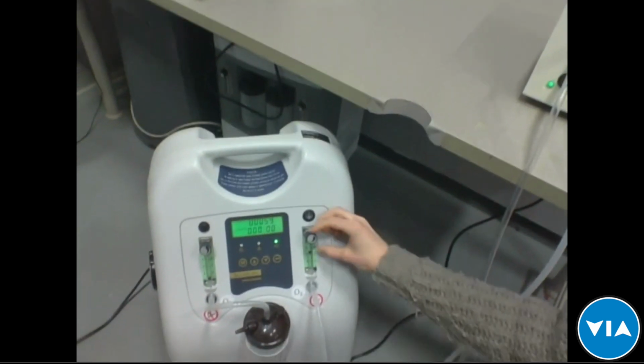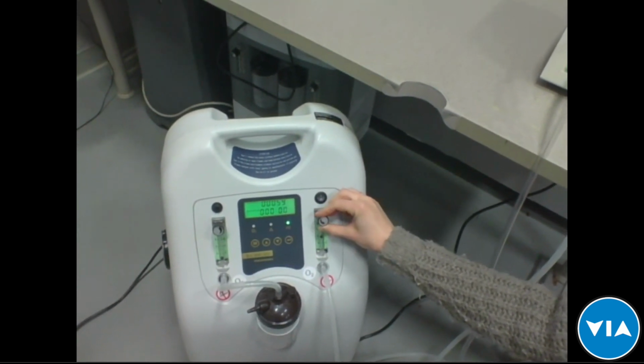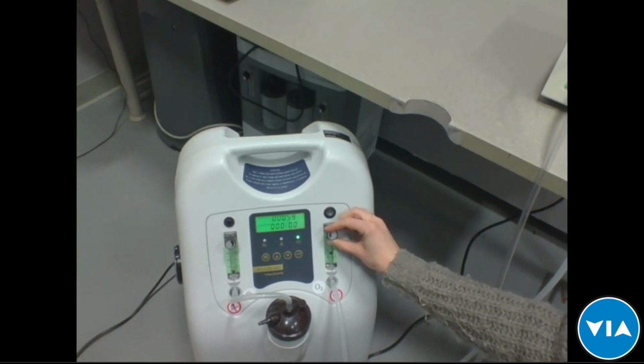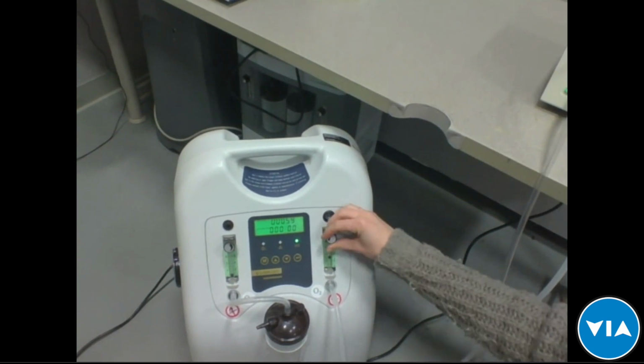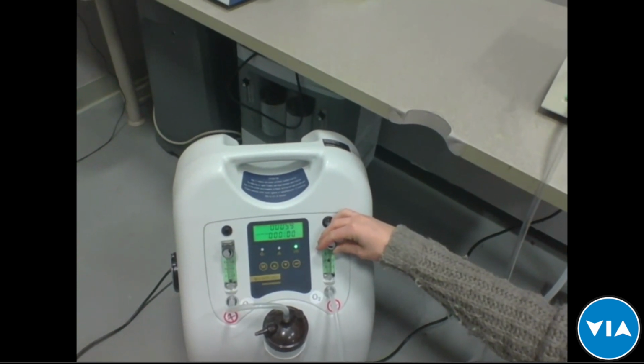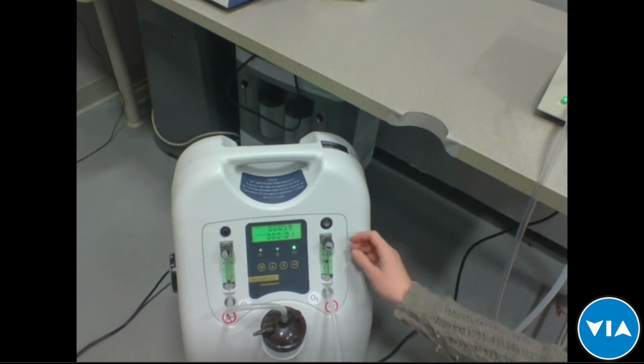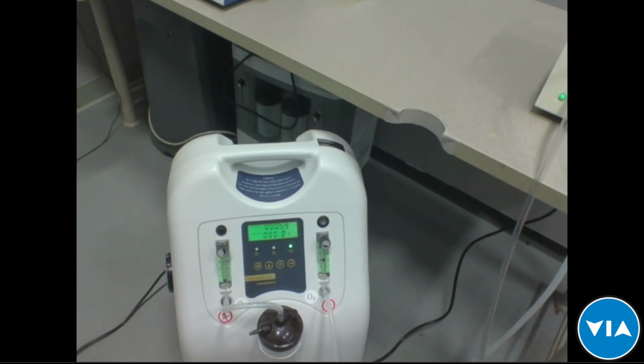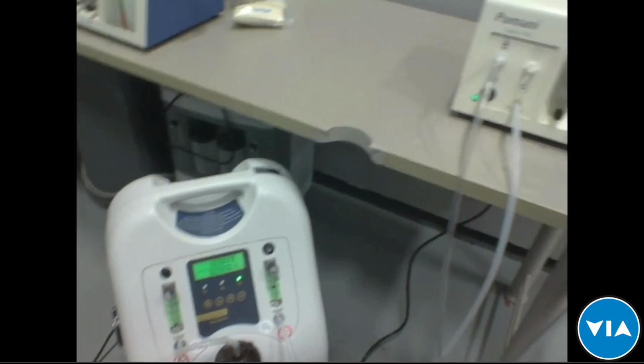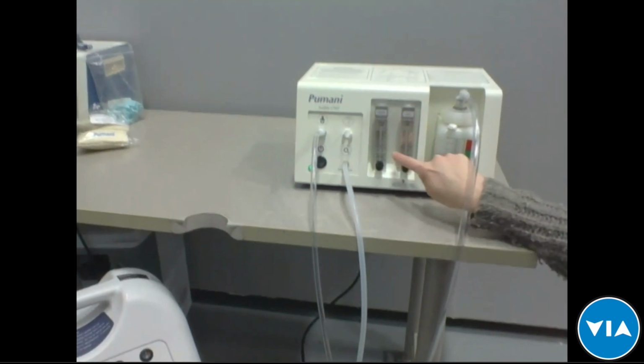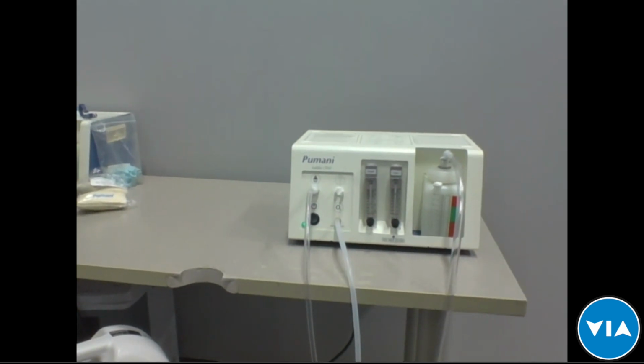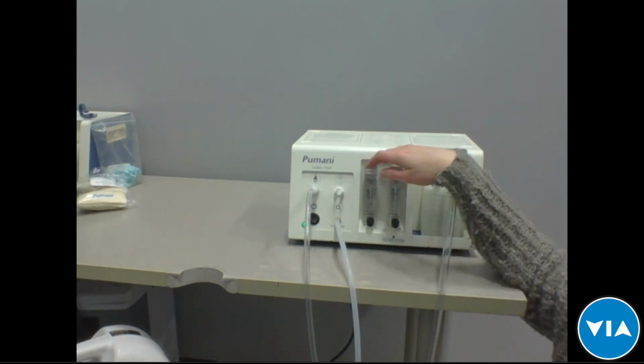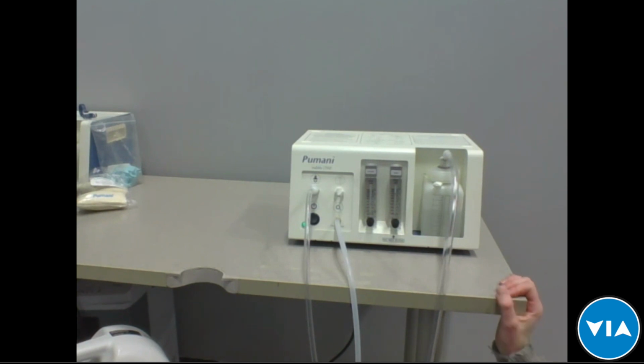Each flow meter and each concentrator have a different type of flow meter, but you do the adjustment on there. And then once you have the adjustment on there, which I think is at 3 liters per minute, what Alexandra is doing, you check back on the Pumani to see what the reading is on the oxygen flow meter. So basically, whatever it shows on the last flow meter, the oxygen flow meter on the Pumani, that is the truth. That's how much flow is coming in through your concentrator.